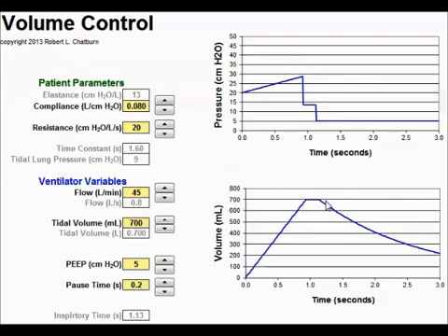And my tidal volume's remaining constant in volume control. So in volume control, when this resistance changes, my volume is going to remain constant. We're going to look at the measured values and see what happens. So I'm going to decrease my resistance to 10. Say that we gave the patient a bronchodilator treatment and it relieved the airway obstruction and it worked.